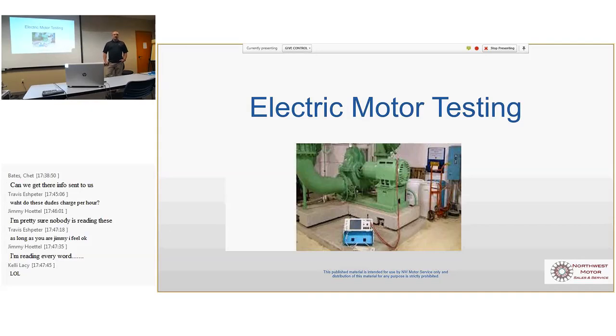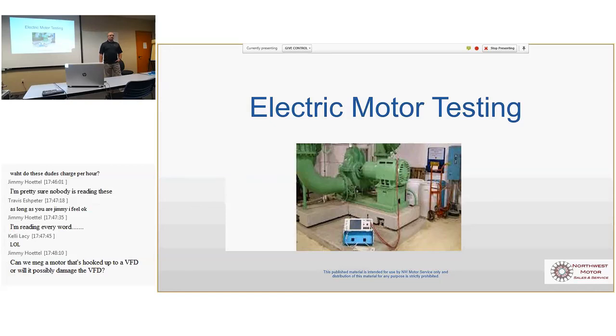There's a really wide school of thought here. So we just did a turbine generator outage with a customer, right? We were testing motors on this turbine generator that really don't make sense. We were testing a $250 motor. It almost costs as much to have Dave out there to test this motor as it does just to replace it. But if that motor fails, it's a lot more expensive than the cost of Dave.